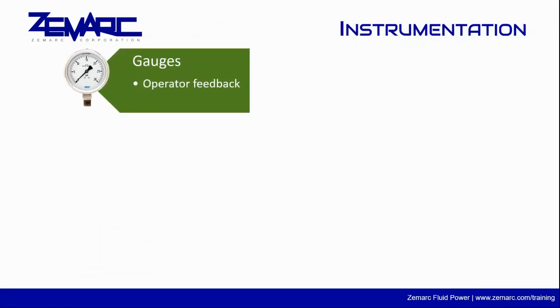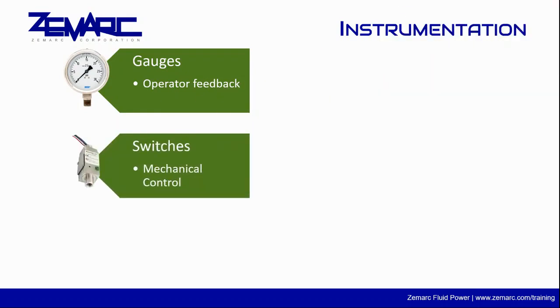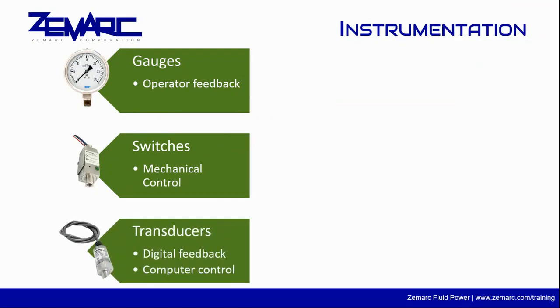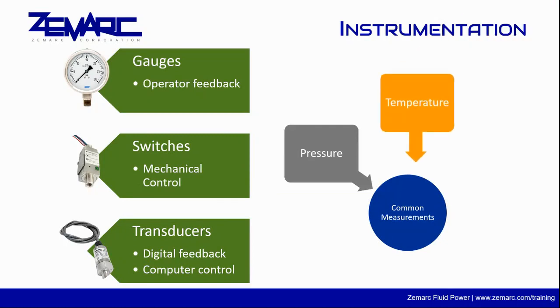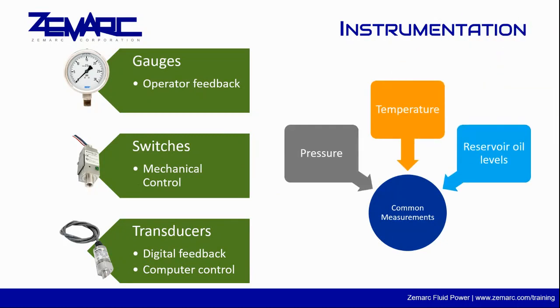Instrumentation sensors give feedback on the hydraulic power unit for safety and maintenance and allows for troubleshooting the system. While not required, they can often help lengthen the system's lifespan. Gauges are useful as they can give feedback in live time for operators. Switches can be used for simple mechanical controls, and transducers give digital feedback that can allow for more advanced computer control. The most common measurements for a hydraulic power unit are for pressure, temperature, and reservoir oil level.